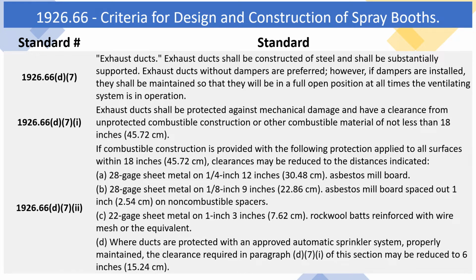(a) 28 gauge sheet metal on 1/4 inch asbestos millboard: 12 inches (30.48 centimeters). (b) 28 gauge sheet metal on 1/8 inch asbestos millboard spaced out 1 inch (2.54 centimeters) on non-combustible spacers: 9 inches (22.86 centimeters). (c) 22 gauge sheet metal on 1 inch rockwool batts reinforced with wire mesh or the equivalent: 3 inches (7.62 centimeters). (d) Where ducts are protected with an approved automatic sprinkler system, properly maintained, the clearance required in paragraph (d)(7)(i) of this section may be reduced to 6 inches (15.24 centimeters).